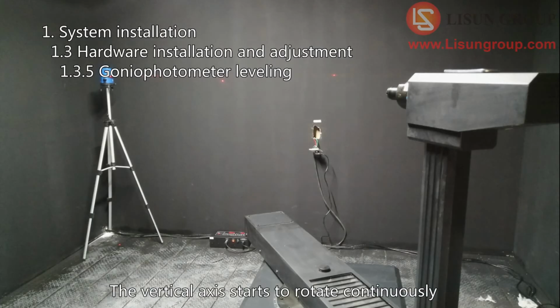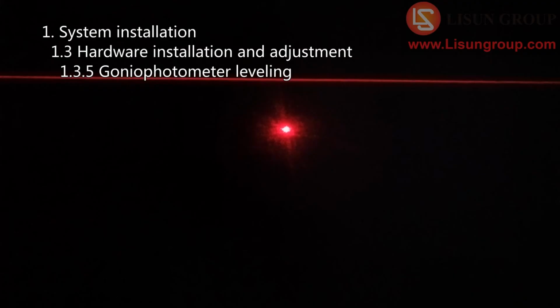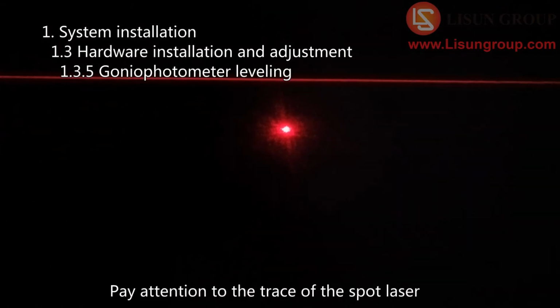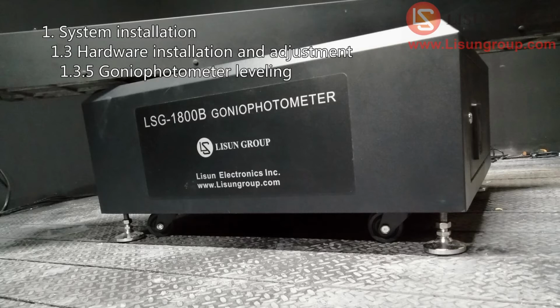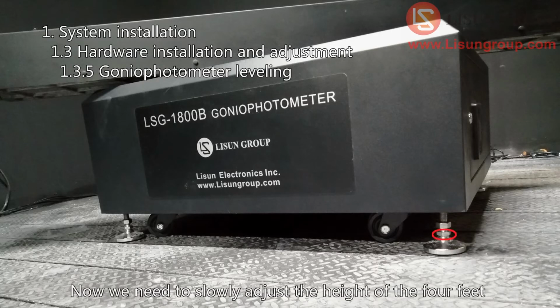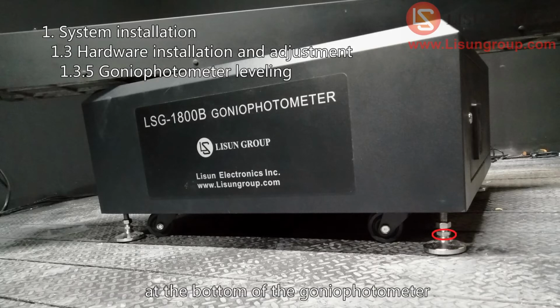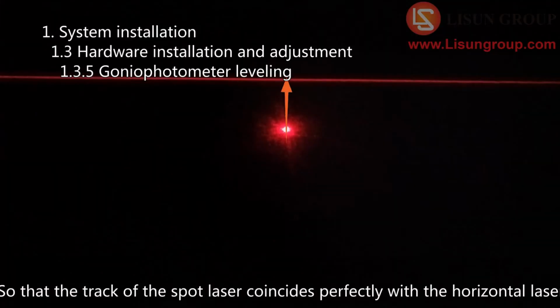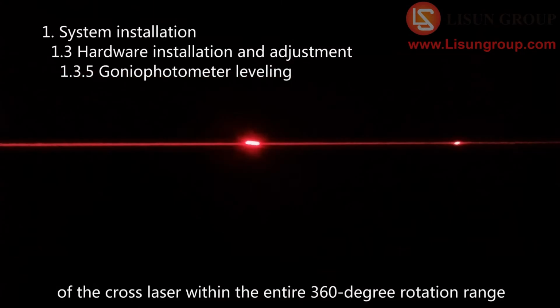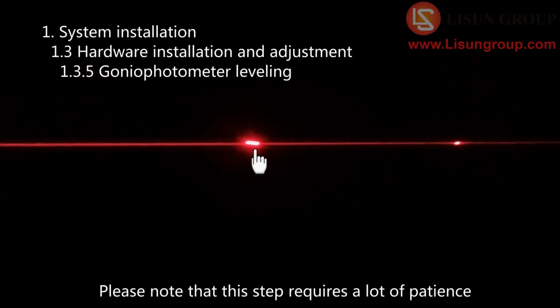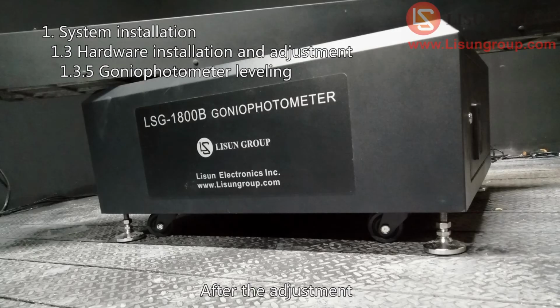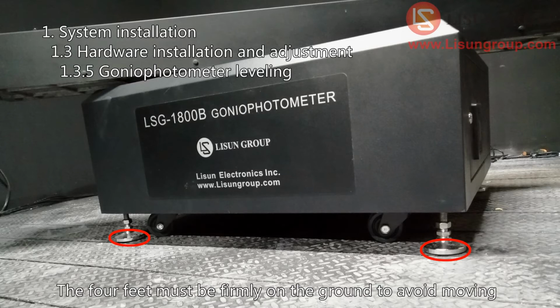The vertical axis starts to rotate continuously. Pay attention to the trace of the spot laser. Now we need to slowly adjust the height of the 4 feet at the bottom of the goniophotometer, so that the track of the spot laser coincides perfectly with the horizontal laser of the cross laser within the entire 360-degree rotation range. Please note that this step requires a lot of patience. After the adjustment, the 4 feet must be firmly on the ground to avoid moving.